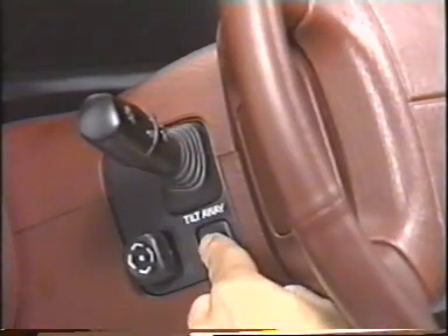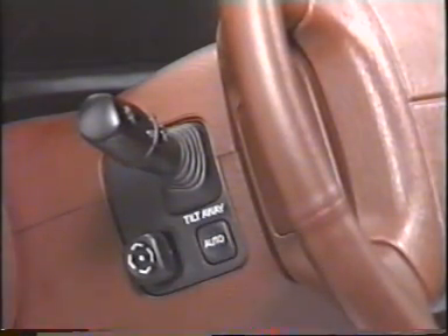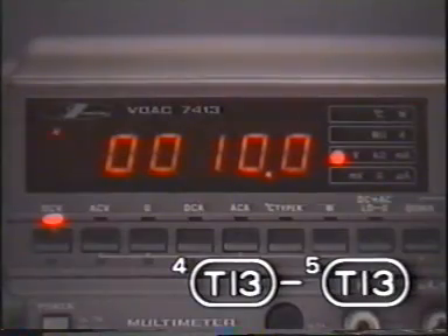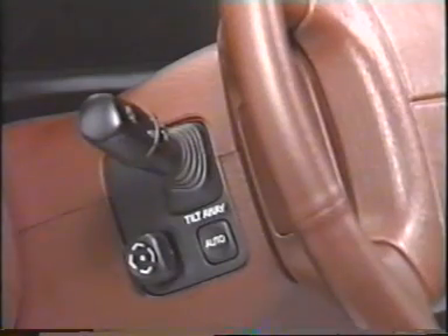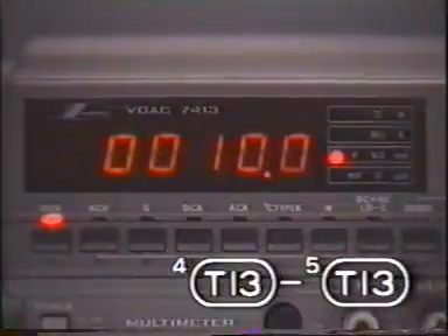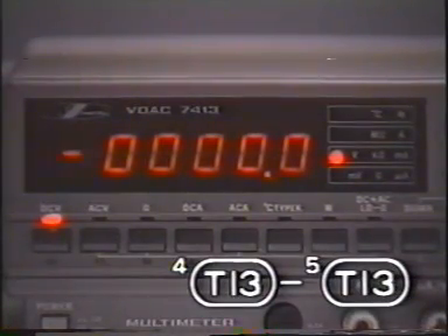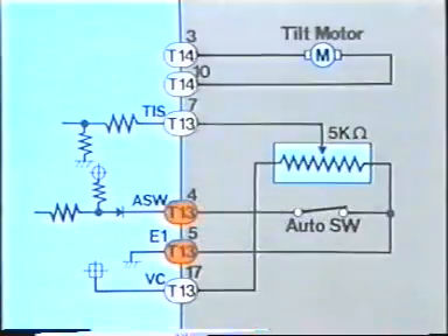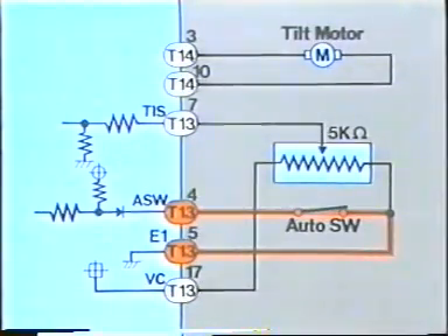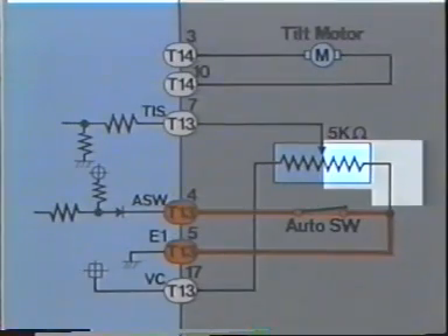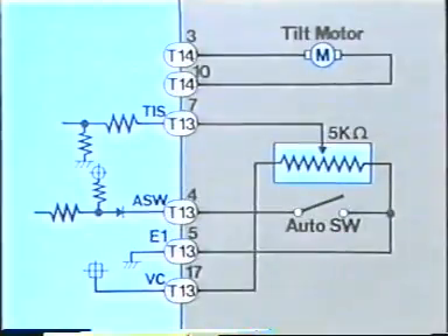When you turn the auto switch on, the meter reading is 10 volts. When you turn it off, the reading drops to 0. It means this circuit is working properly. So if there is an open somewhere, it's probably in here. You can prove it by moving the tilt sensor by hand and see how the voltage changes between TIS and E1.